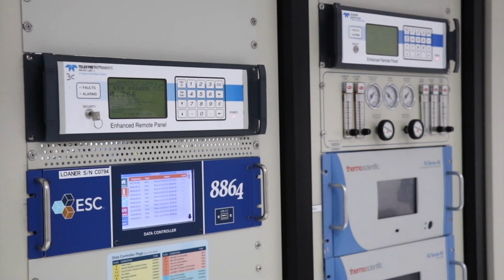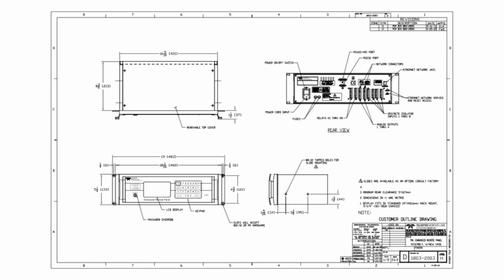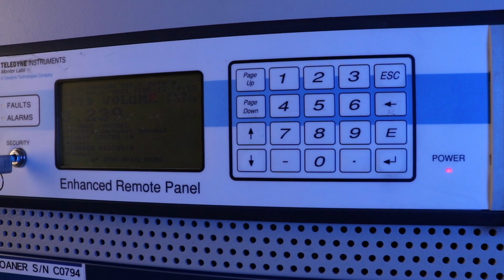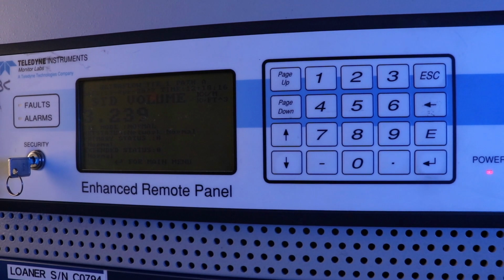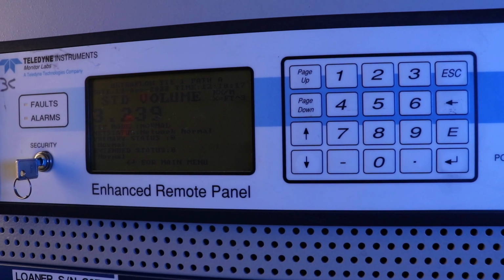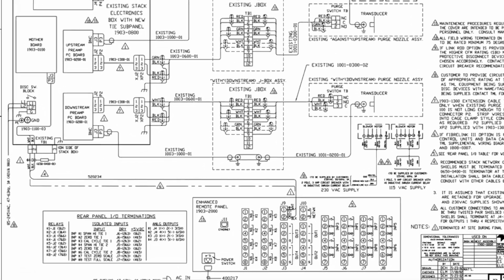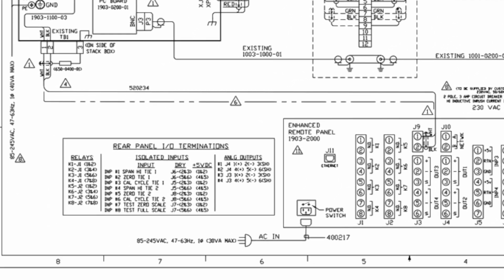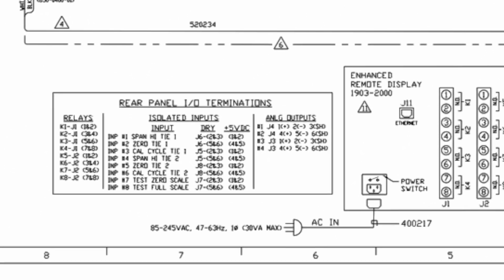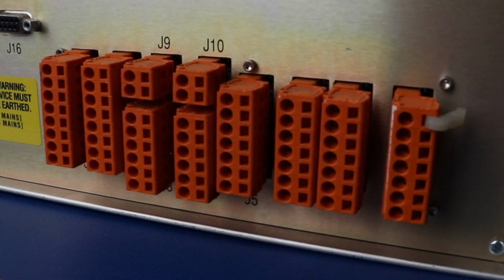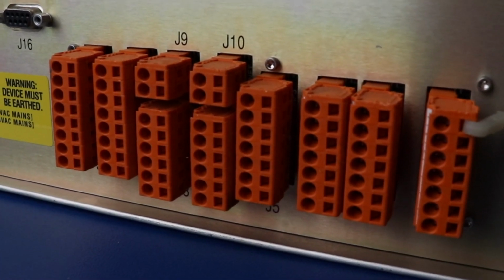Lastly, the Enhanced Remote Panel, or ERP, is a 19-inch rack-mount display and control unit. It features a touch-sensitive keypad, an LCD display, key lockout, serial and network communication node. The multi-I/O board has 8 relay outputs, 8 isolated digital inputs, and 4 individually isolated analog outputs. All of the ERP I/O are connected on the back panel with pluggable connectors.